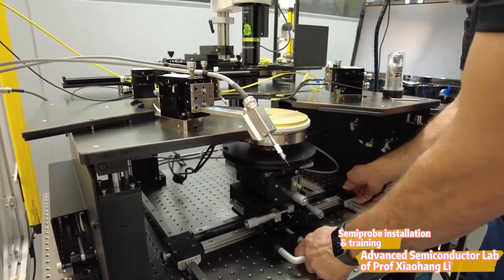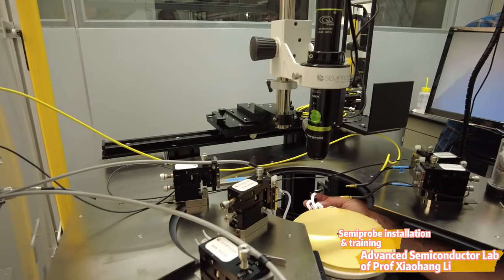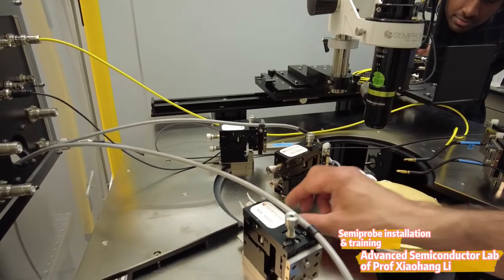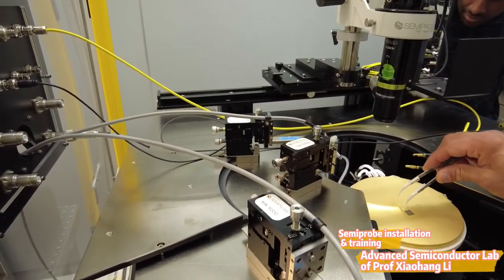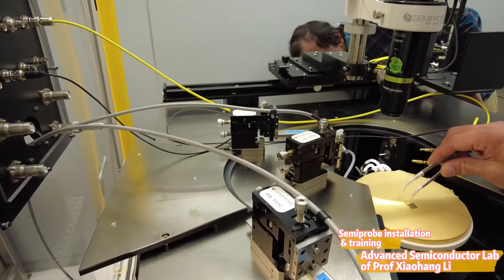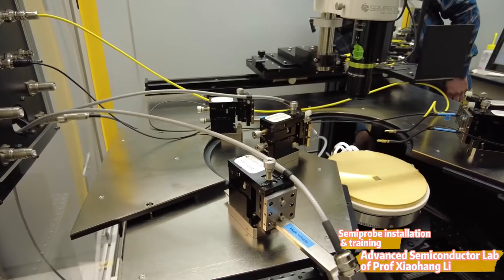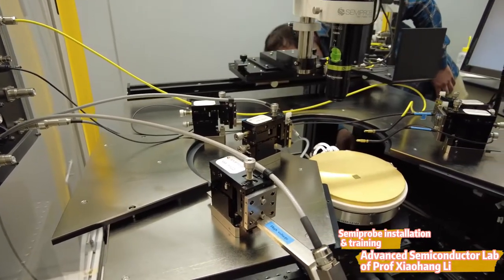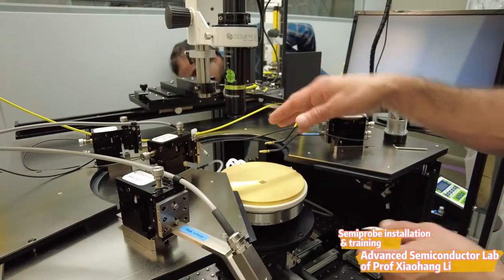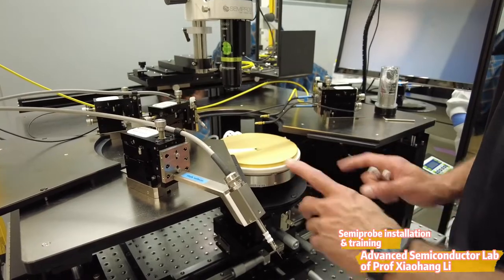For connections in the back, there are three vacuum connections: 150 millimeters (the outer), 75 millimeters, and the middle. The middle is for a small part — if you only have a small part you want to measure, you can turn just those three on and they'll hold the part. There are three on/off switches for the vacuum. The bottom layer is connected straight to the vacuum and it's always on to hold everything down.